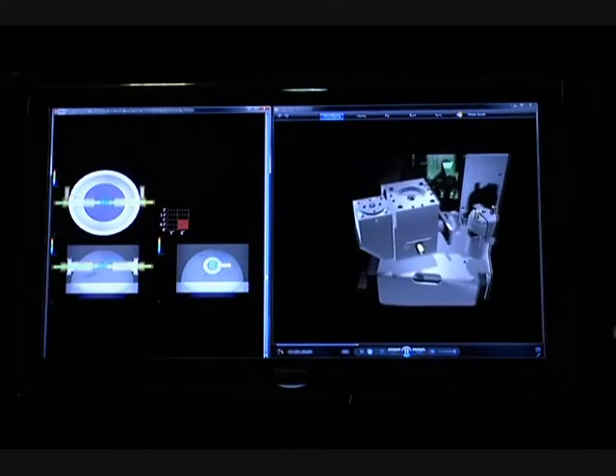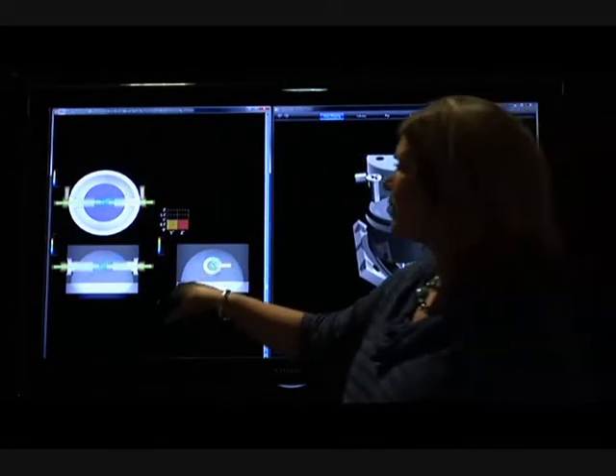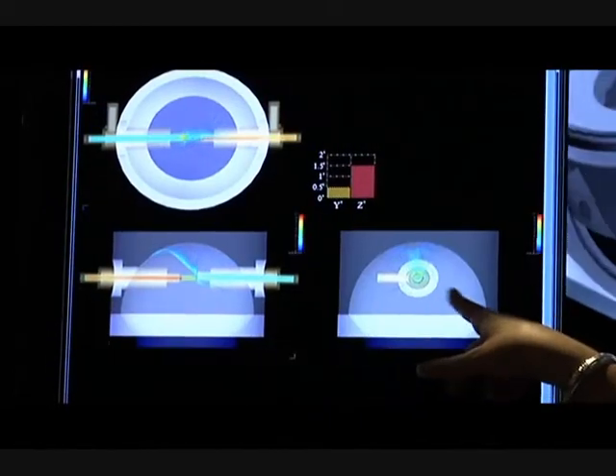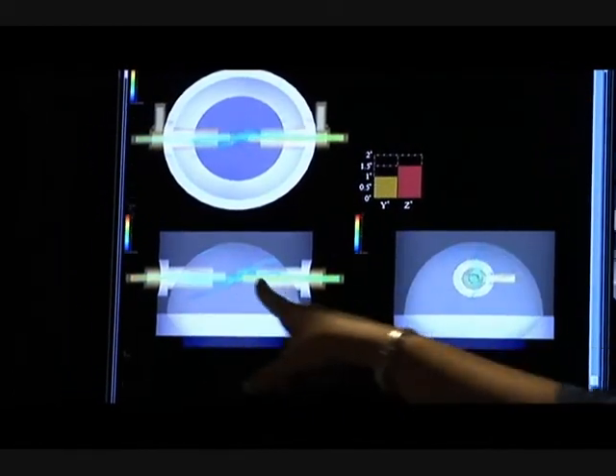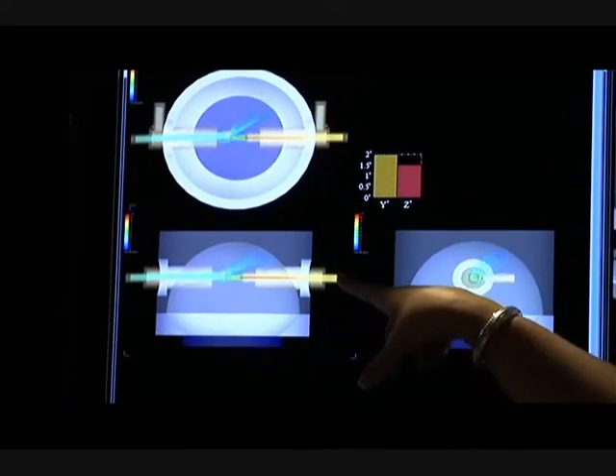Custom low-cost optics then direct the fluorescence light to photomultiplier tubes. Novel photon counting electronics process this signal and reduce it to the measured number of detected biological particles. This information is then passed to an internal algorithm to determine the alarm status.